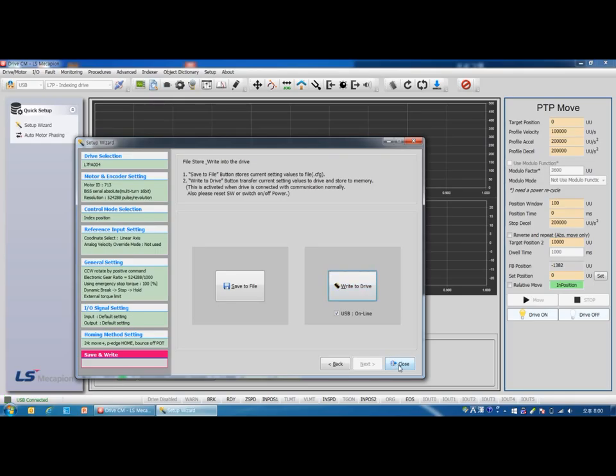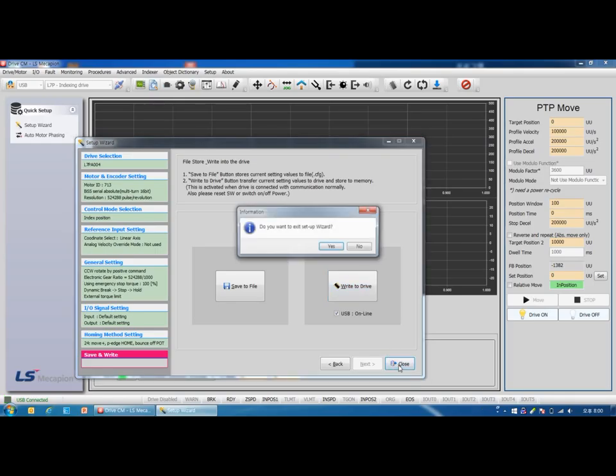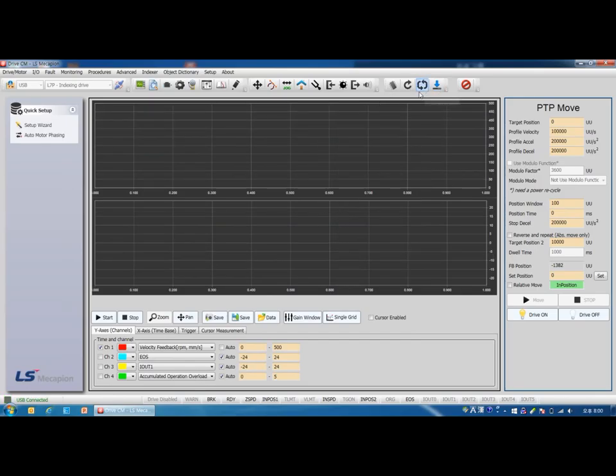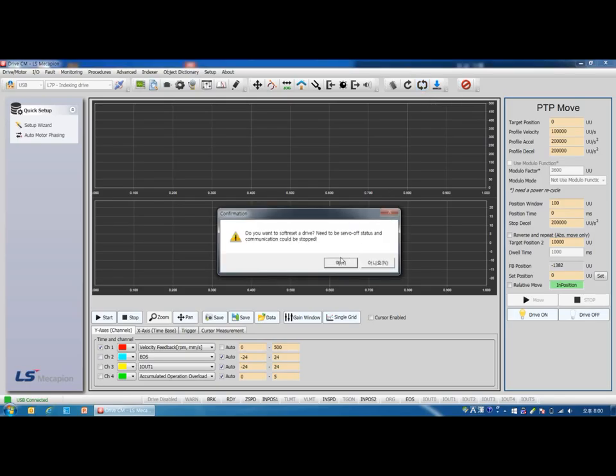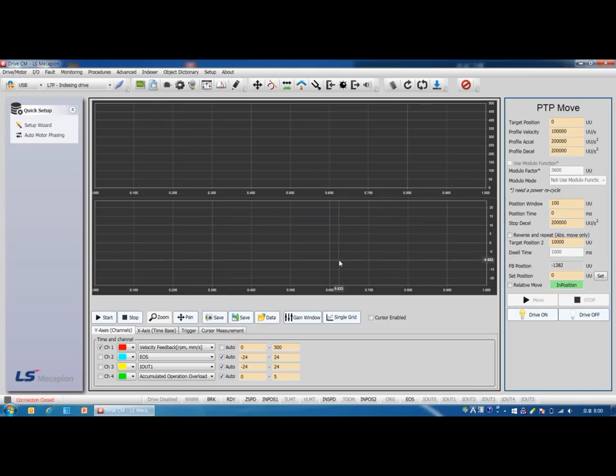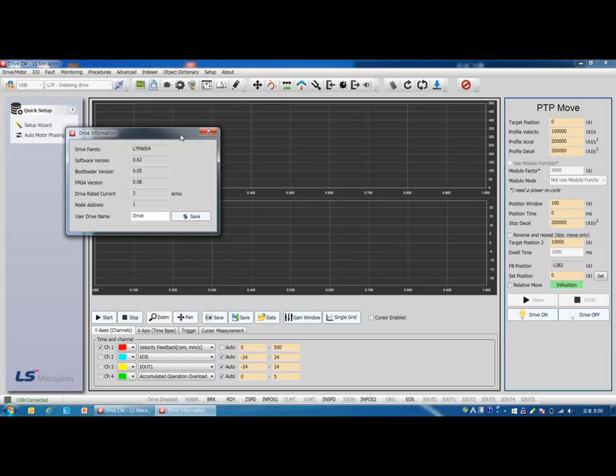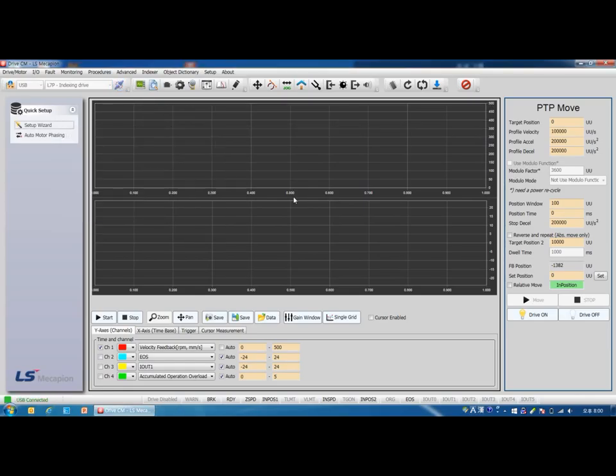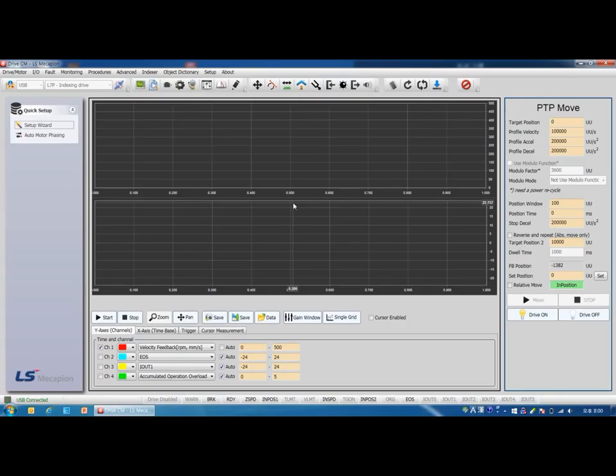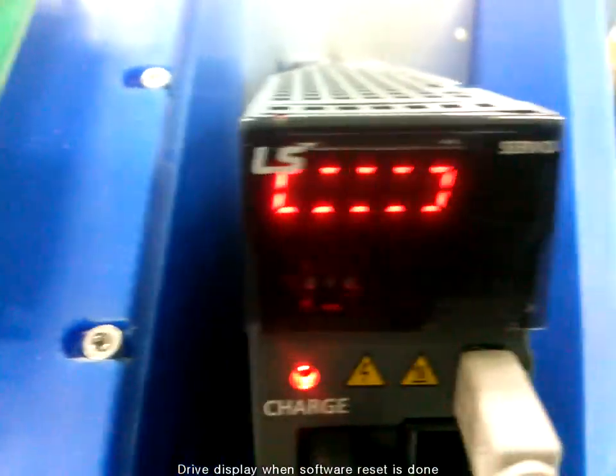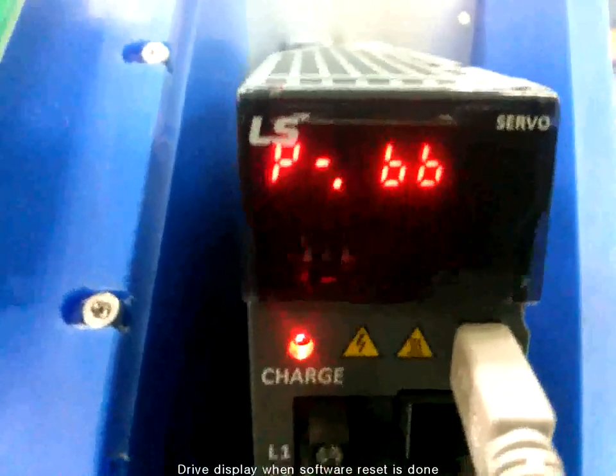Click write to drive, and close. Click yes. After setting the parameters, be sure the power is turned off and on, or perform a software reset. This icon is the software reset function. Yes. After software reset, communication is disconnected, so start communication again. This is how to set up basic parameters by setup wizard.